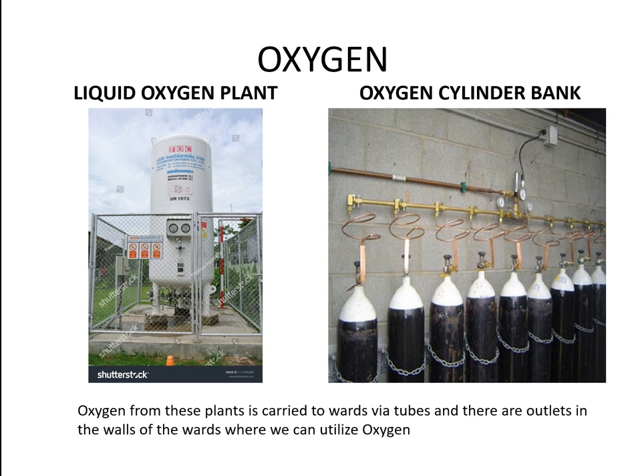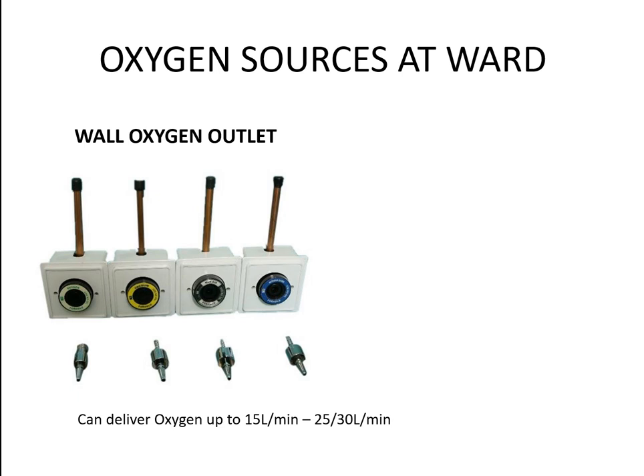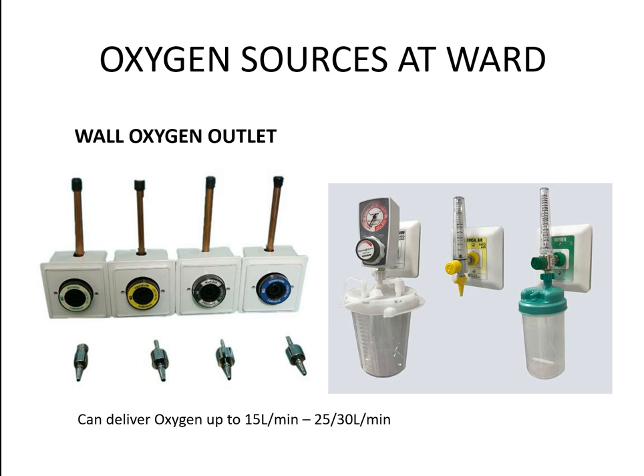So the oxygen which is carried from these plants will be utilized in the ward in this manner. We have a wall oxygen outlet, and in this wall oxygen outlet we can use oxygen. Just having the wall oxygen outlet won't be enough. We need certain things called oxygen regulators. If you can see my cursor, there's something like a bottle and a flow meter. These are called oxygen regulators. Since it is attached to the wall oxygen outlet, these are called wall oxygen regulators. Without these regulators, we can't utilize the oxygen being supplied by the wall oxygen outlet.